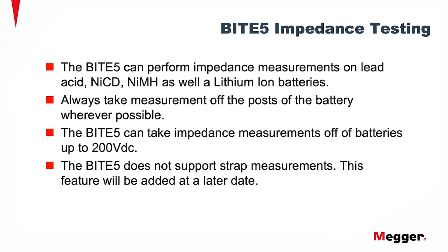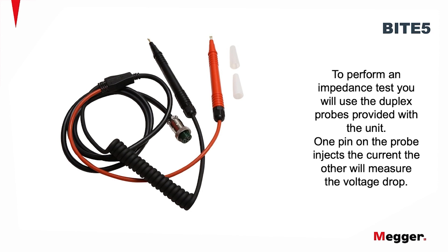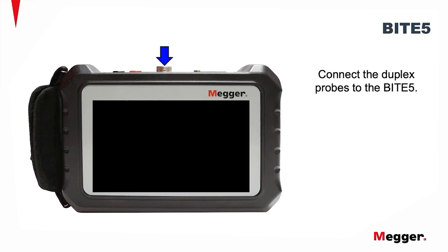The BITE5 does not support strap measurements. This feature will be added later at some date. To perform an impedance test, you'll use the duplex probes provided with the unit. One pin on the probe injects the current, the other will measure the voltage drop. Connect the duplex probe to the BITE5.